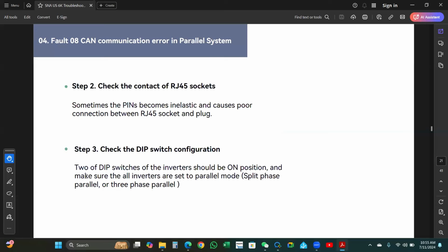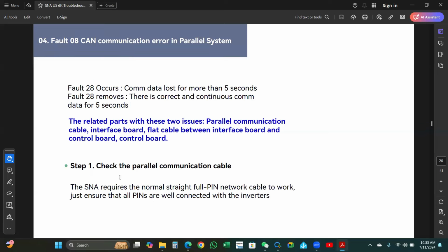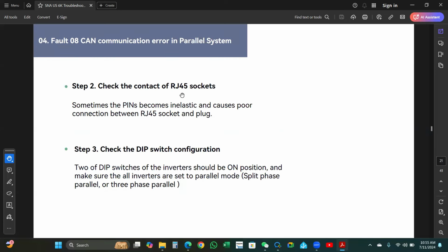Step 1, check the parallel communication cable. The SNA requires a full-pin network cable to work. Just ensure all the pins are well connected with the inverters. Step 2, check the contact of the RJ45 socket. Sometimes the pin becomes inelastic and causes poor connection between the RJ45 socket and plug. Step 3, check the dip switch configuration. 2 of the dip switches of the inverter should be in the on position, and make sure all the inverters are set to parallel mode, split phase parallel or 3-phase parallel.